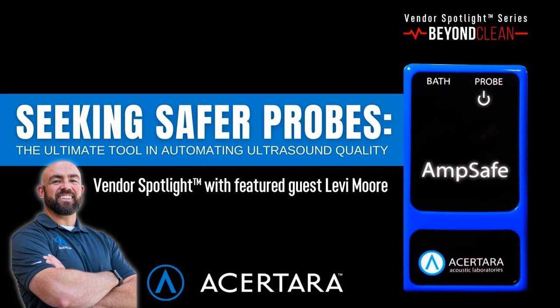And to us, that drives us to make sure that the equipment is functioning correctly and that there's not going to be any safety issues associated with it. Because like you were saying in electrosurgery or minimally invasive surgery, the device can malfunction, or you can have errors that happen that cause problems. And actually what we're talking about with TEE probes and electric leakage is the primary area that's concerned with. And when you have improper levels of electric leakage, you can actually burn the esophagus. And of course, it creates other issues where there's opportunities for fluid ingress. But we take all those things. We take a very holistic approach to what we're looking at in each aspect of our business to get that sort of cross-pollination between the things that we're working on to bring those best practices in.